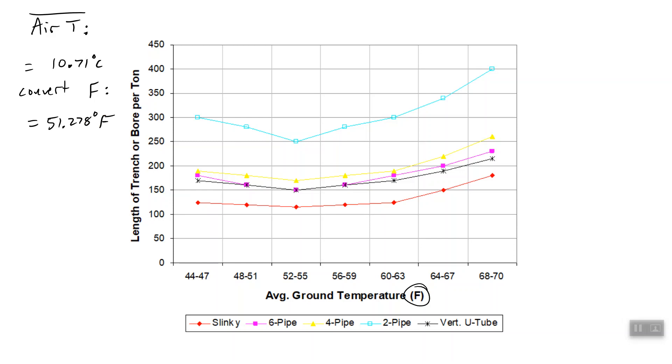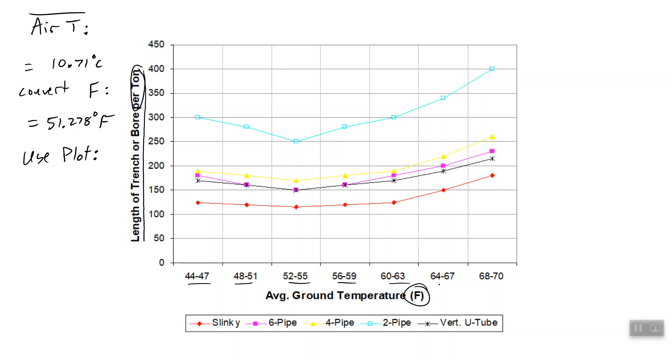Okay, so now what we're going to do is we're going to use the plot that I gave you in class, which is the length of a trench or borehole per ton of cooling. And then we find these are different average ground temperatures, which correlates to the average air temperature. So we have 51.278 degrees Fahrenheit.